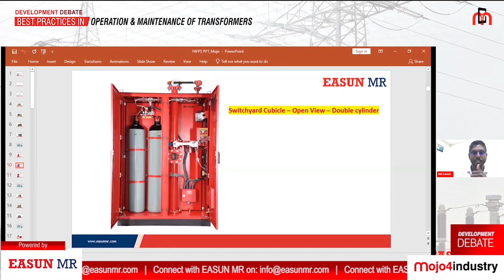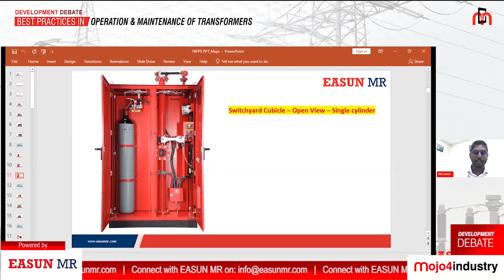See, there are two types of systems which we offer. For the transformer which has more than 40 MVA capacity, we offer two nitrogen cylinders of 50 kg. And for the transformer which has a capacity below 40 MVA, we offer a single cylinder, which is quite enough to protect the transformer from fire.